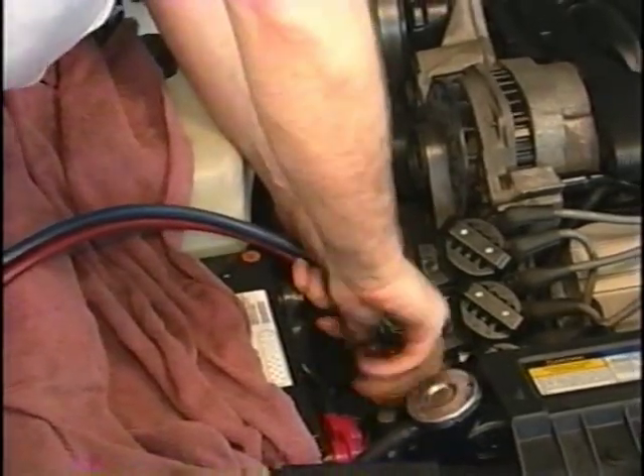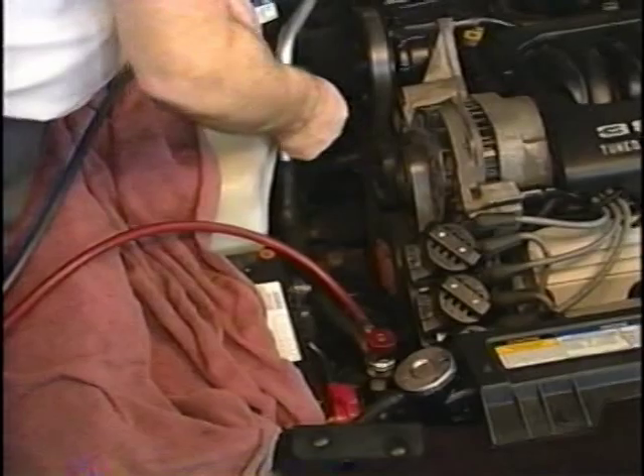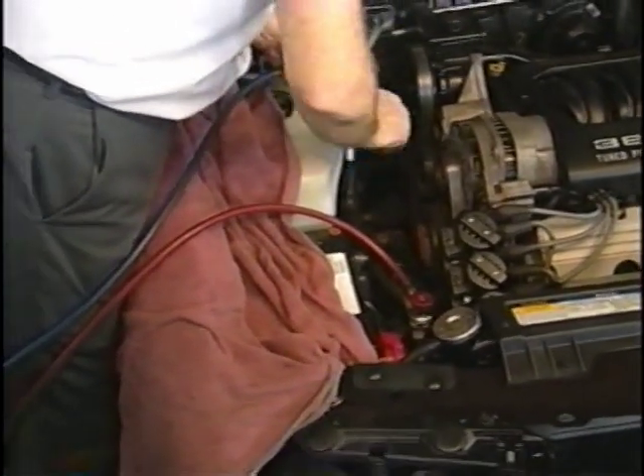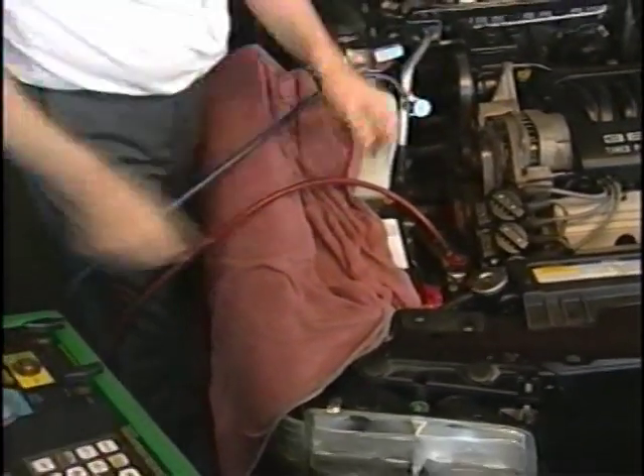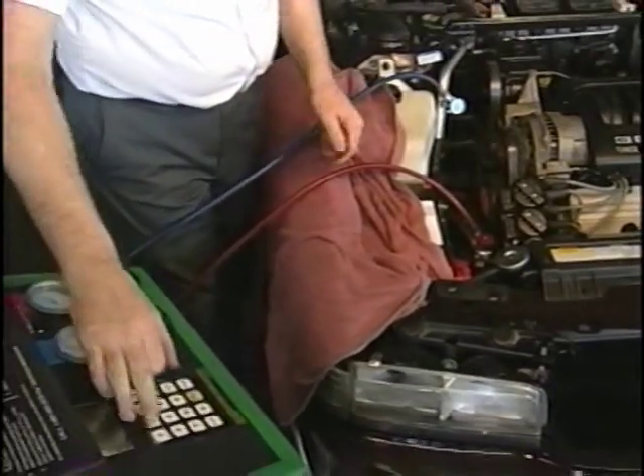And then you can go ahead and put a vacuum on it, and that gives you an idea of how much, if it holds vacuum or if it doesn't, if it leaks off fast or if it holds it. If it holds vacuum, it normally won't have much of a leak.